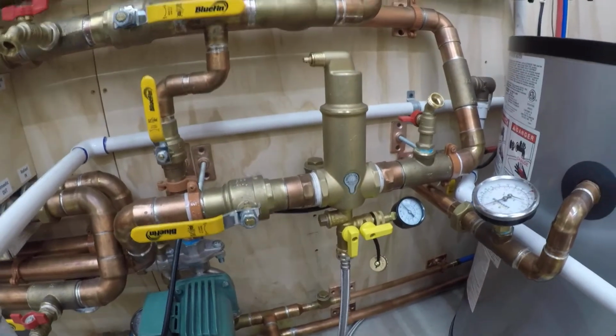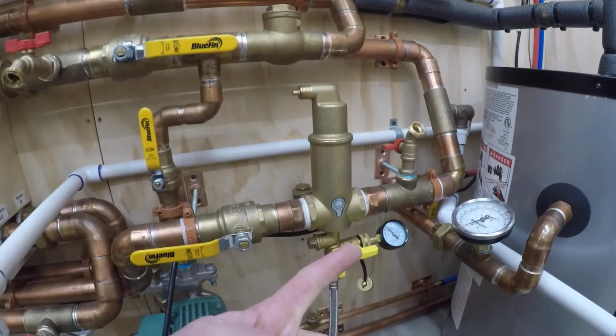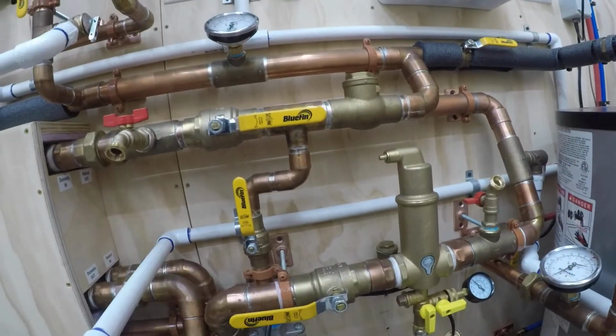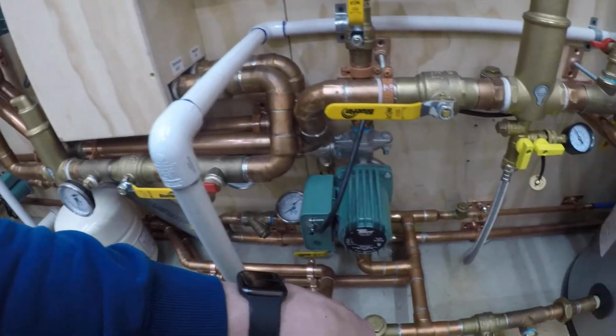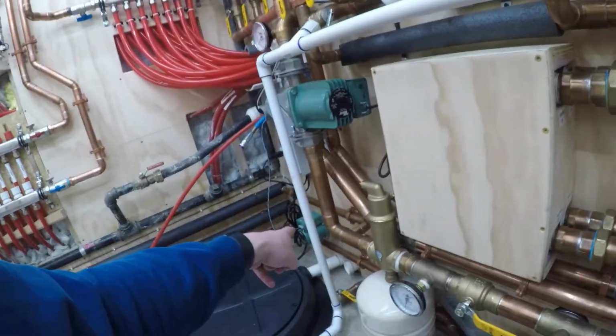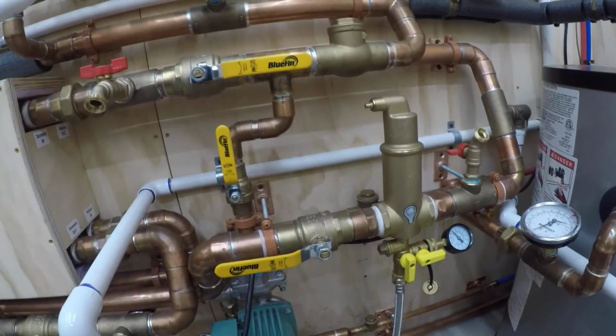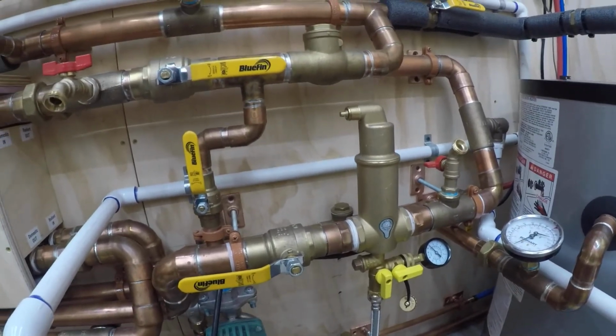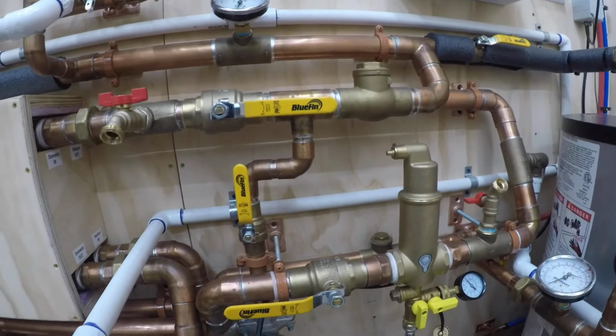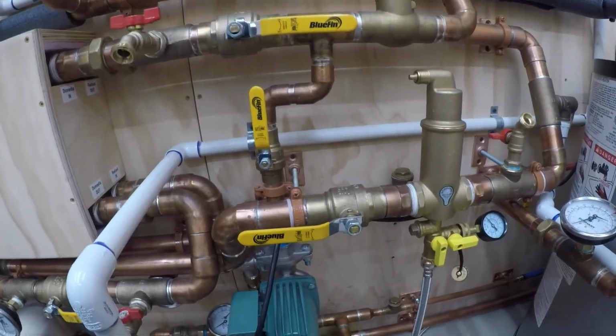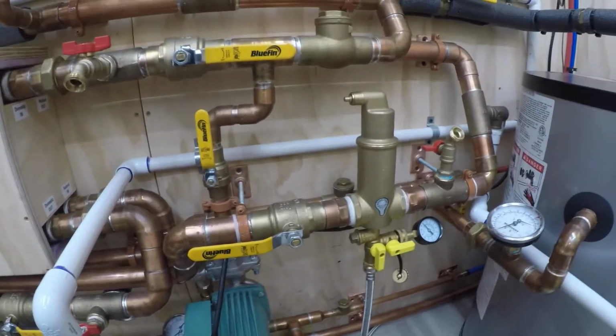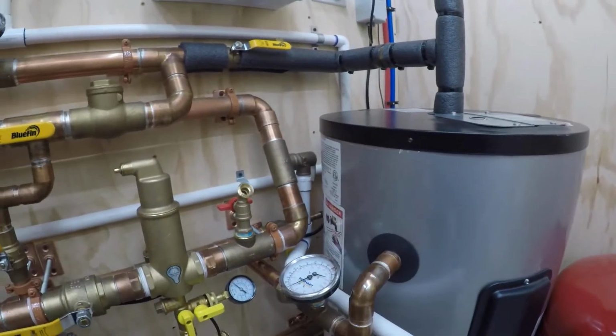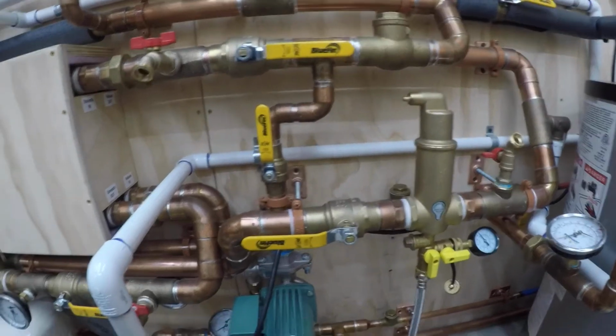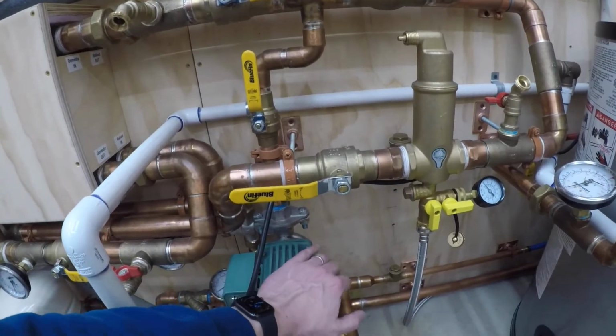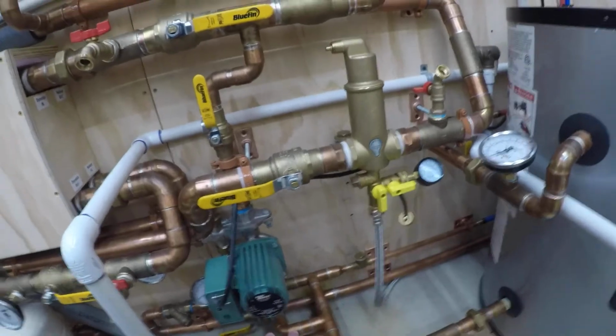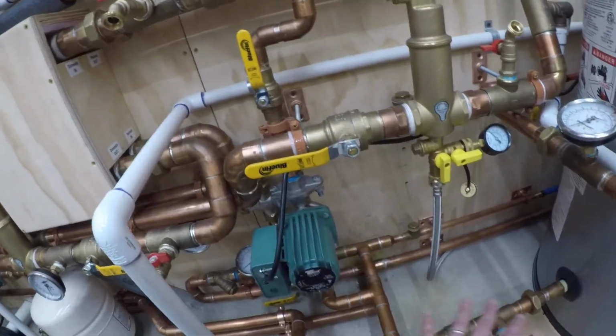So it is possible that the furnace could be on, recirculating the tank, and the hot water heaters won't be on. It's possible that the hot water recirculation loop, like it just was, could be on, and the heaters won't be on. Again, this is one of the reasons it's possible somebody could be washing their hands, or the dishwasher could be on, and things could be pulling from this tank and the tankless units won't fire. The only thing that will fire them is they see the flow of this pump. So that's kind of this neutral area that I talked about.